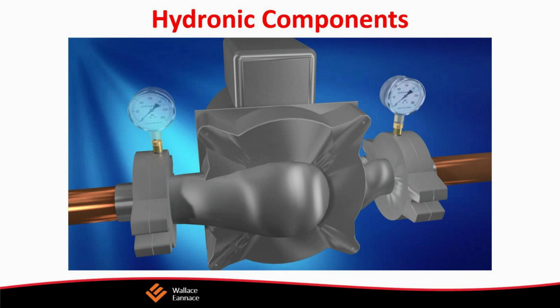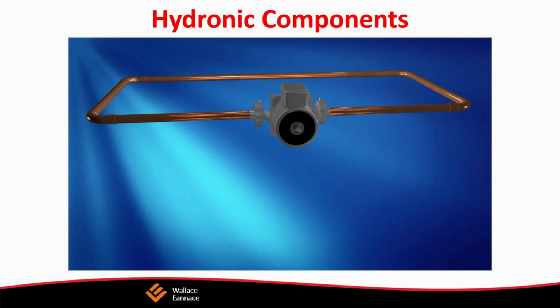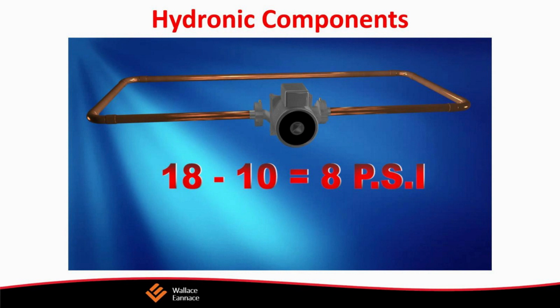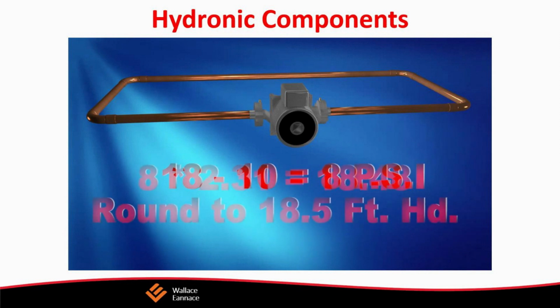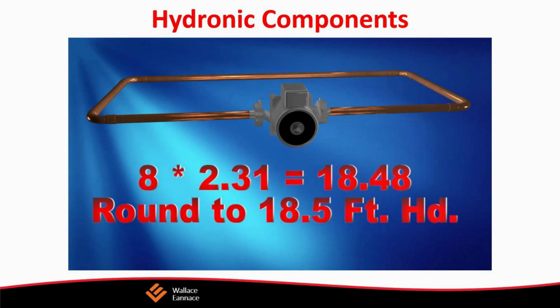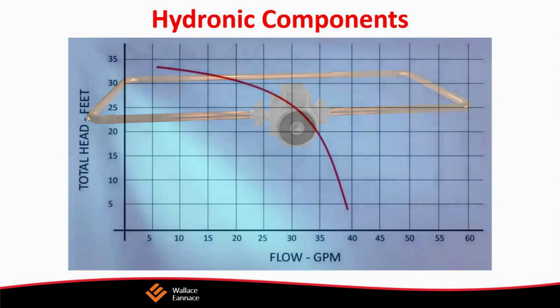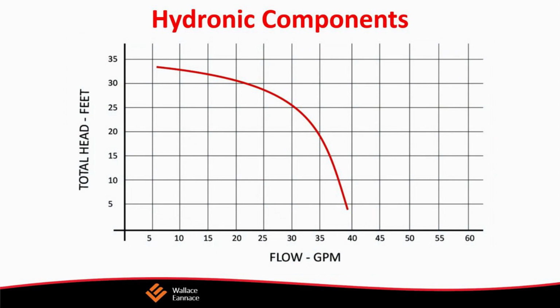The pressure at the center of the impeller drops, and the pressure on the outside of the impeller rises. This creates a delta P, and Mother Nature takes over from there. In nature, everything seeks equilibrium. So the higher pressure we have just created seeks out any lower pressure. The suction side of the circulator provides just that. This means the pressure coming out of the discharge side of the circulator seeks the suction side. And since we are in a closed system, it has a direct path back to the circulator. And now we have flow.